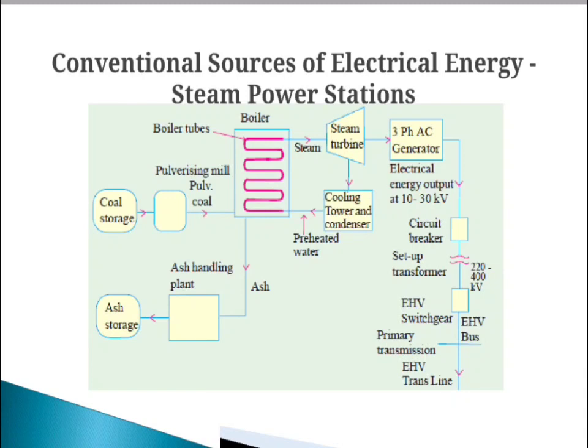Then the next one is the generator. This is the main unit of the power plant. In this unit, generation of electricity is done, and it is mechanically coupled with the turbine, so as the turbine rotates, it also rotates. The speed of the generator is given by N = 120F/P in RPM, that is revolutions per minute. Here N is the speed of the generator, F is the frequency of the system, and P is the number of poles of the system.